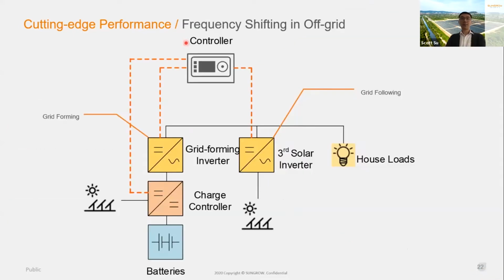Okay. So the next one is off-grid modes. Here, this diagram is a very typical off-grid system. Firstly, you shall install a grid-forming inverter. Also, you should install the charge controller, and the charge controller has two terminals. One will connect to the PV arrays. Another one will connect to the batteries. The second one is optional. It's a third-party solar inverter. And also, you shall install a microgrid controller to control the grid-forming inverter, charge controller, and the third-party solar inverter.